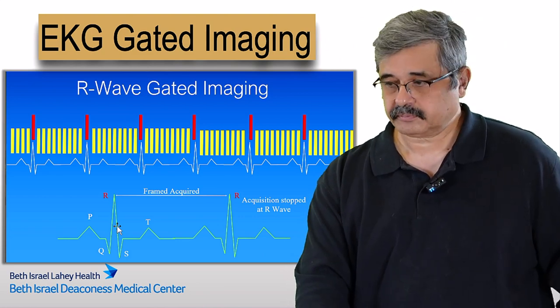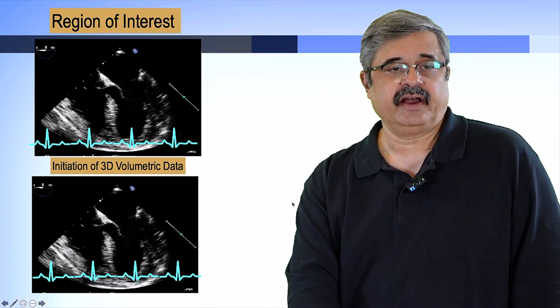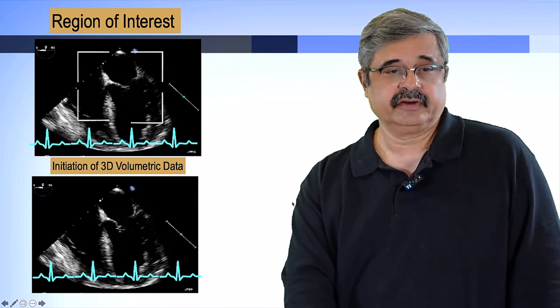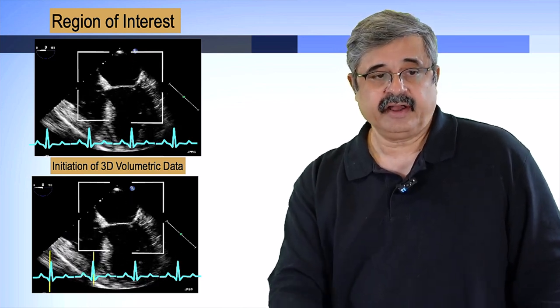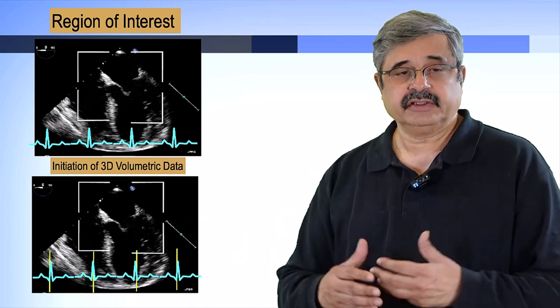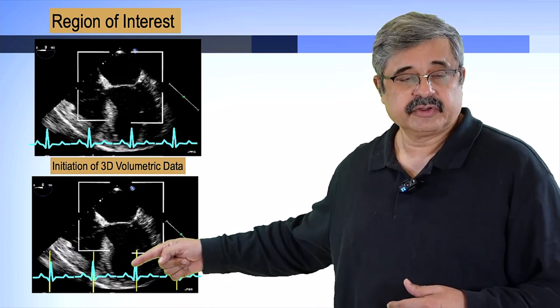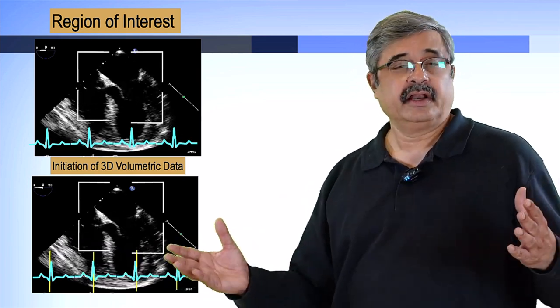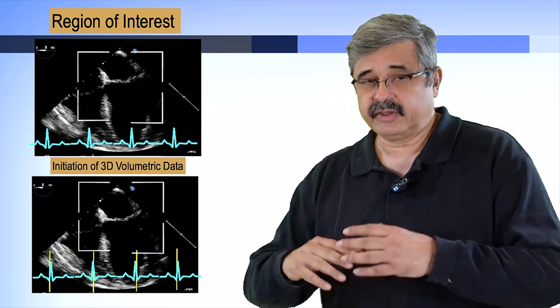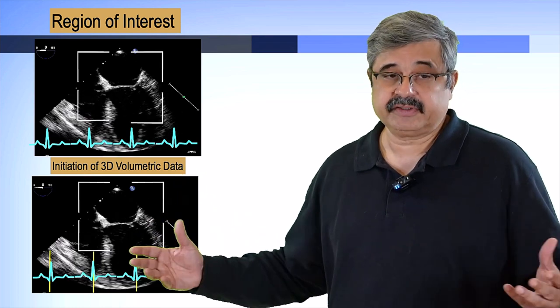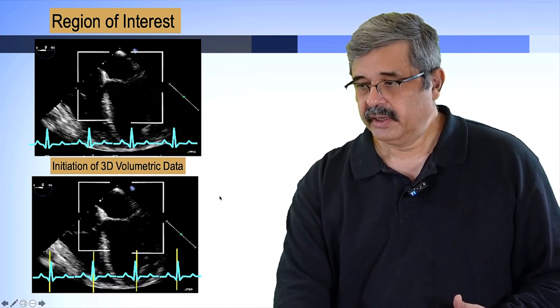The region of interest — the mitral valve — is identified first. Then three-dimensional volumetric data acquisition begins, which includes identifying R waves on the EKG signal being fed to the machine. It was not just important to display the EKG; the computer had to be told to recognize the R waves. You knew it was working when you saw yellow spikes on the R waves, indicating the computer was recognizing them. A lot of things could break down at any moment, and if you didn't know to activate R-wave recognition, the entire operation could fail from simply not pressing one button.